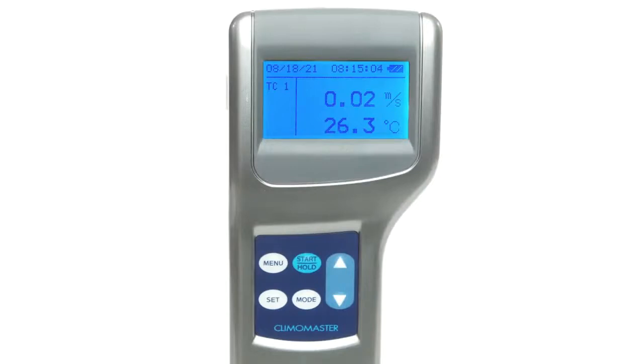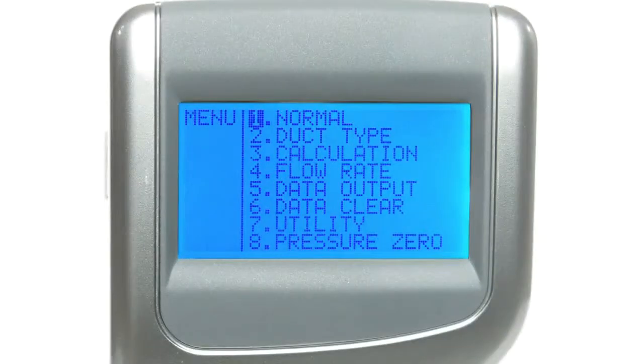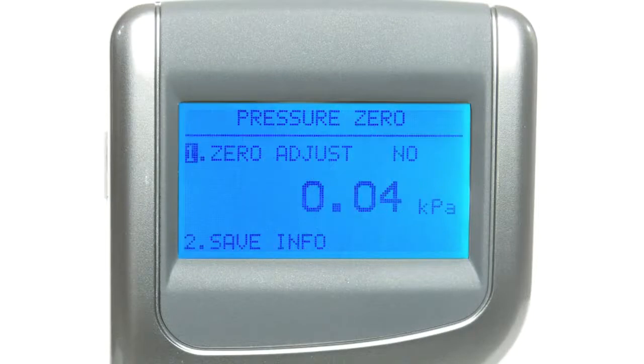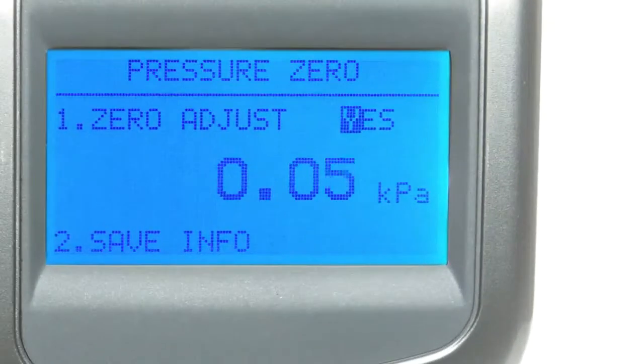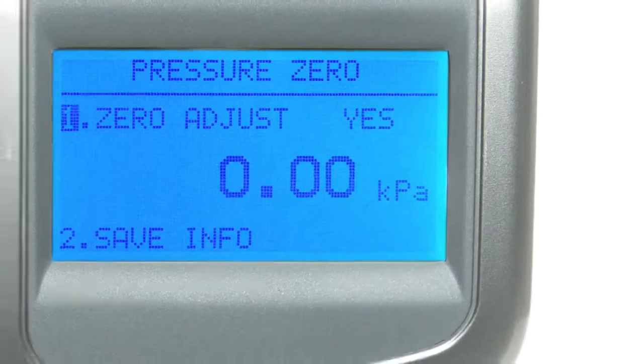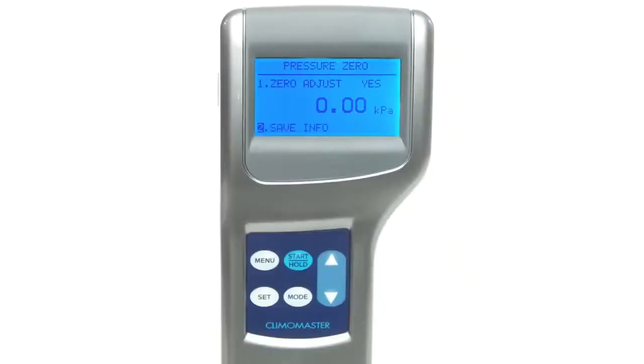Press the menu button to enter the main menu. Using the navigation buttons, scroll down to pressure 0 and press set. Use the navigation buttons again to highlight zero adjust. Select it by pressing set, then scroll until you see yes and press set to see the pressure return to 0.00 kPa. Scroll down to highlight save info and press set. And that's it.